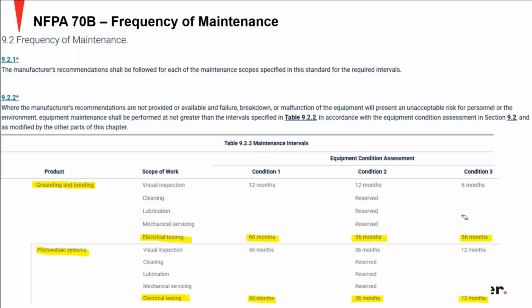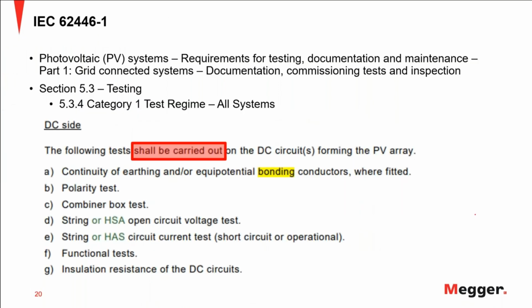So I have here the frequency of maintenance. NFPA also shows the frequency of maintenance, and for grounding and bonding, it shows all electrical testing shall be done according to this schedule: 60 months for condition 1, 36 months for condition 2, or 36 months for condition 3. And it also talks about photovoltaic systems. So different parts of this standard tell you that in photovoltaic systems you need to do it.